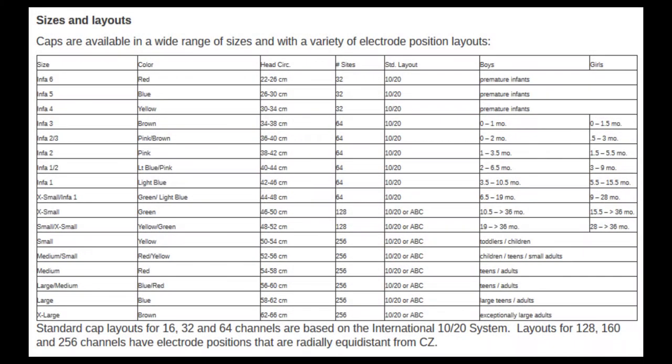Choose a cap size with a stated range that puts the participant's head circumference right in the middle of the range. A cap that is too tight will make the participant uncomfortable. And a cap that is too loose will result in poor recording quality, since a loose cap will not hold the electrodes tightly against the scalp.